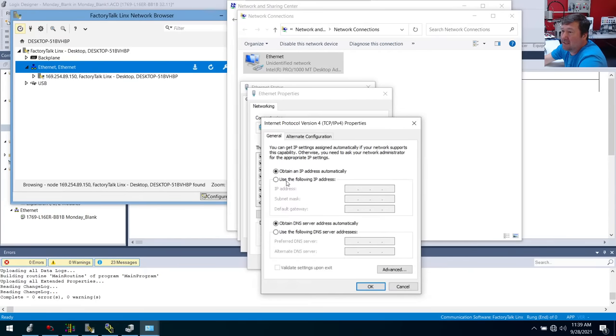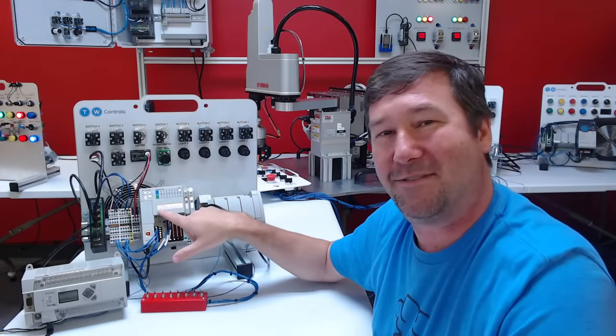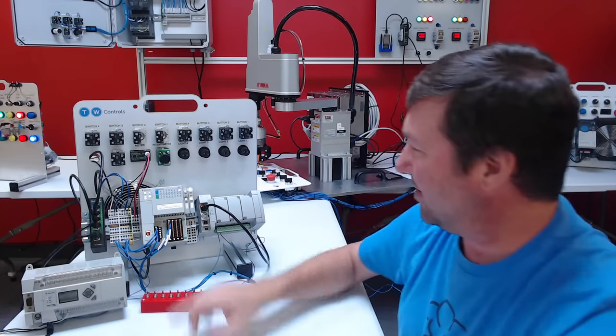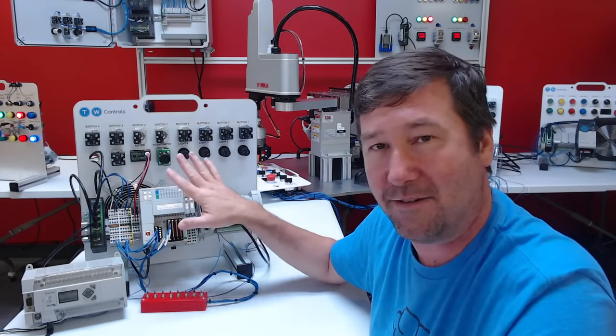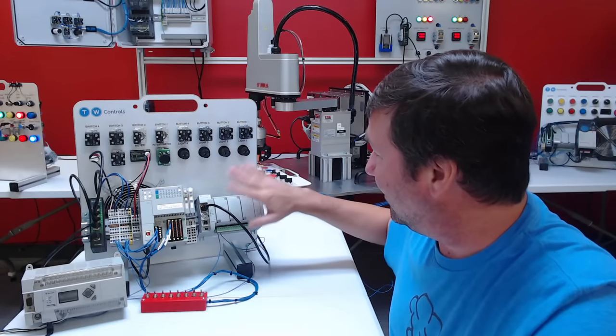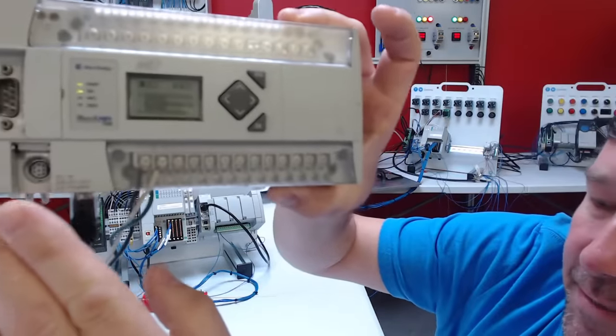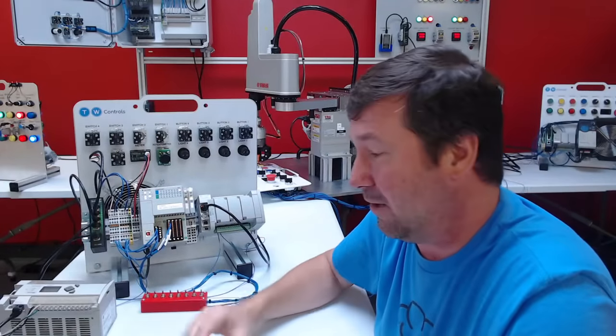We see we've got Obtain IP address automatically — it's looking for somebody to tell it what IP address to use. Well, we don't know it. This is the time that you really need to keep track of your IP addresses. One thing I love about the CompactLogix in our training classes: everybody points at that MAC address right away — it says ENET address, that's got to be it. Well, no, that's a MAC address, it's not going to help us out. And somebody will probably tell me in chat, some of them have a display. This one has a great display right here, but this morning I noticed the display buttons have gone out. So even if it has a display, you better have it written down somewhere.